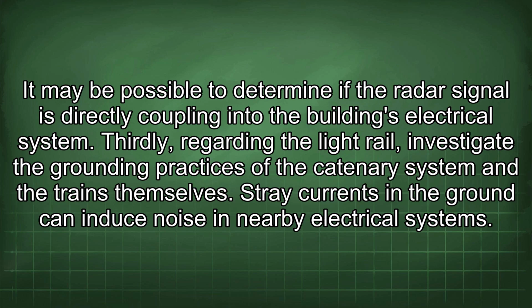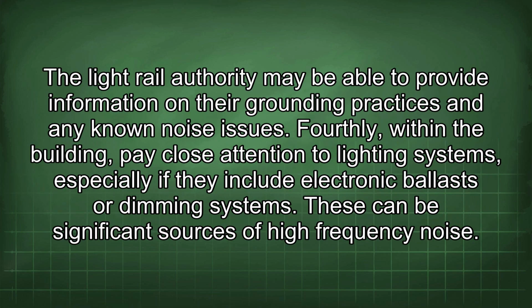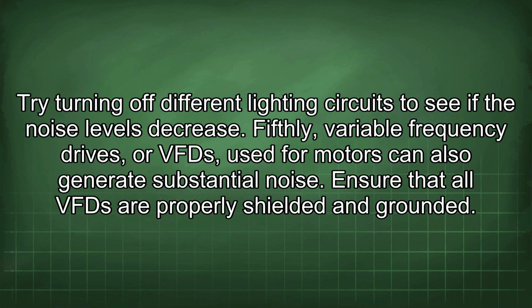Thirdly, regarding the light rail, investigate the grounding practices of the catenary system and the trains themselves. Stray currents in the ground can induce noise in nearby electrical systems. The Light Rail Authority may be able to provide information on their grounding practices and any known noise issues. Fourthly, within the building, pay close attention to lighting systems, especially if they include electronic ballast or dimming systems. These can be significant sources of high-frequency noise. Try turning off different lighting circuits to see if the noise levels decrease.